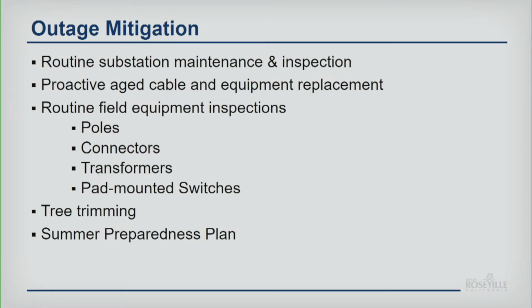We also do proactive replacement of aged cable. This mainly is for mainline cable, which is the main distribution trunks off of our substations. We focus there because of the outage numbers: you might have 1,000 or 2,000 customers on a feeder. So we like to proactively replace that as we collect data and analyze it.